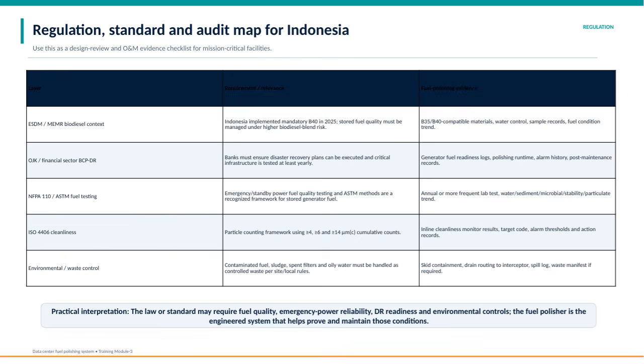Starting with the regulation side, Indonesia has mandated the use of B40 biodiesel blends starting in 2025. This means facilities must carefully manage stored fuel quality because higher biodiesel blends carry increased risks. To address this, facilities need compatible materials for B35 or B40, control water content in the fuel, maintain sample records, and track trends in fuel condition.